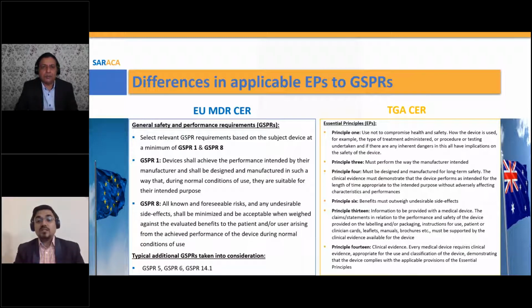Then principle 13: information to be provided with a medical device. This covers all the packaging inserts, including the IFUs, meaning instructions for use, labeling, any clinician cards, any leaflets, any manuals, whatever goes with the device. And there is a specific requirement for this packaging insert only. So it's also a basic requirement.